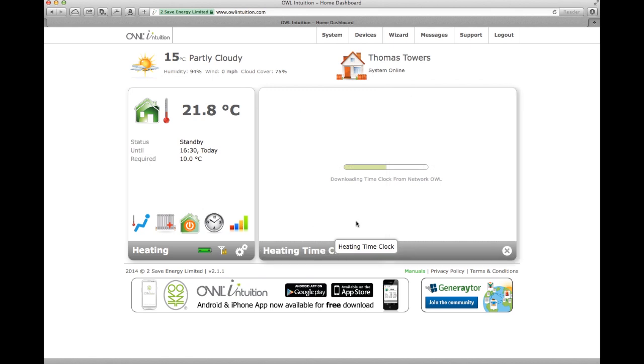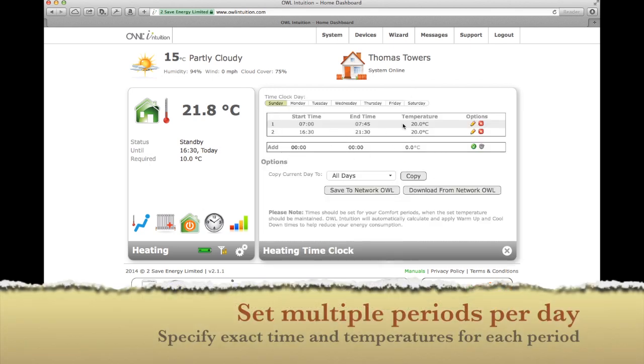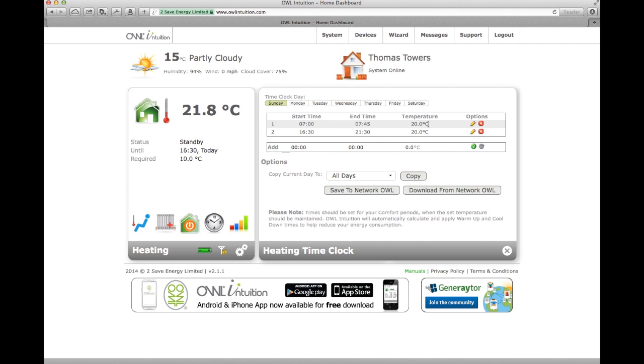If I configure the time clock, this is a far more precise way of controlling your heating than the old half-hour or 15-minute timers. This allows you to say, for example, between seven and 7:45 in the morning heat to 20 degrees, between half four and half nine in the afternoon heat to 20 degrees — specified down to the minute and to the precise degree. You can do this across multiple settings, different days, and even a seven-day schedule. Once you've changed it all, you click save to network and it's set.